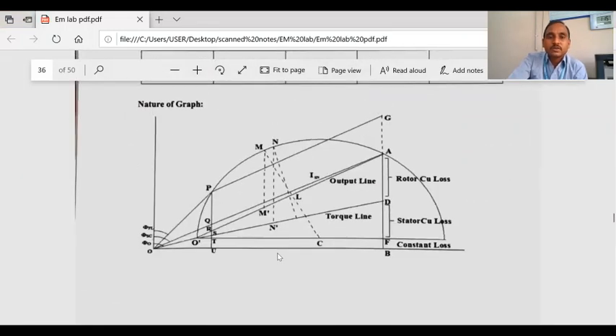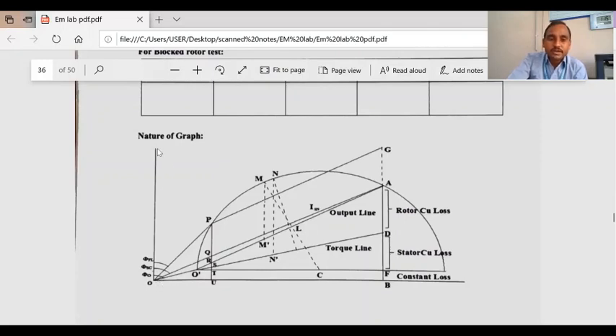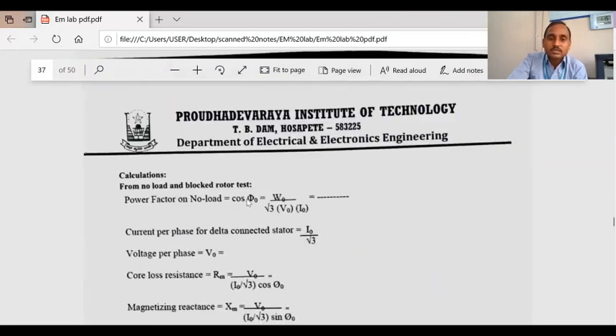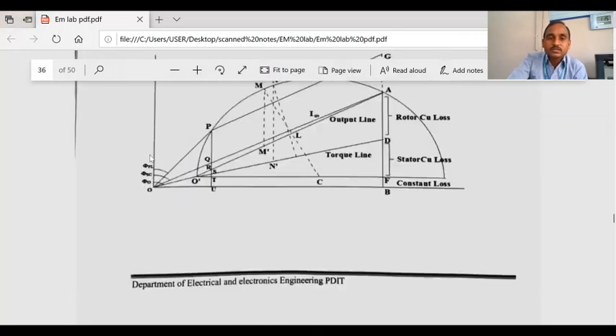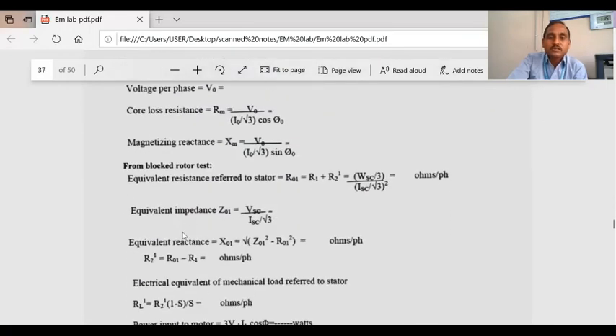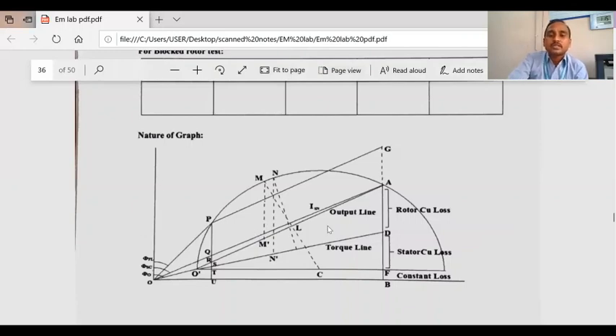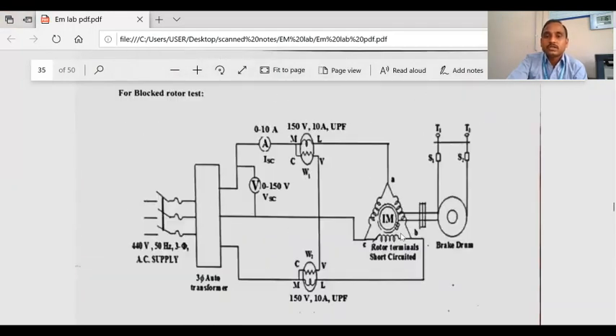After calculation, we need to draw the circle diagram. The circle diagram is drawn on the x-axis and y-axis, with the angles and the corresponding I naught drawn. The phi naught angle is calculated from cos phi naught; the cos inverse of the answer gives phi naught. Similarly, phi sc is calculated from cos phi sc. Okay. So as mentioned in the theory part, the circle diagram is drawn along with these measurements. From the circle diagram, we will obtain the rotor copper loss, stator copper loss, and constant losses, and draw the torque line and output line. So we will get the maximum torque and maximum output that can be achieved by means of the nature of the graph, which is called the circle diagram. Okay. So this is about the no load and blocked rotor test of a 3-phase induction motor.